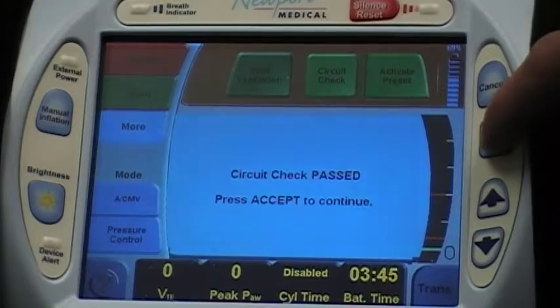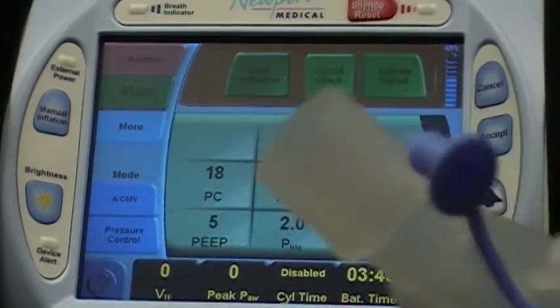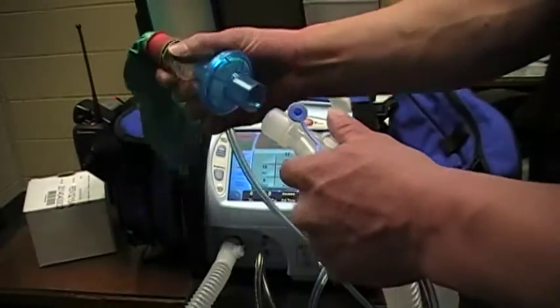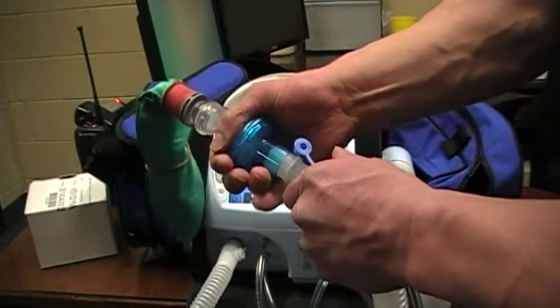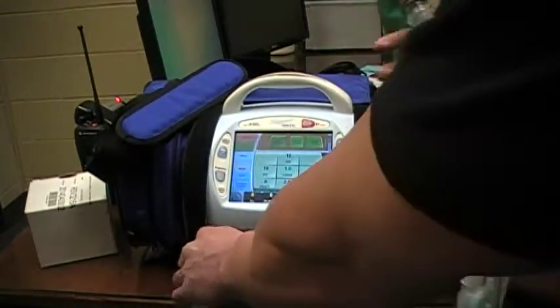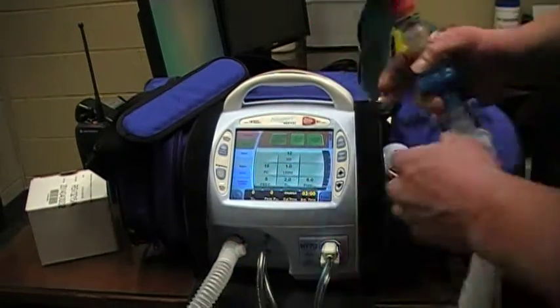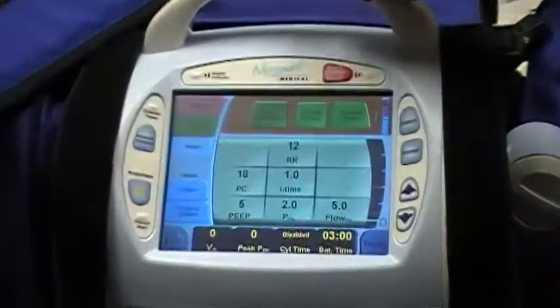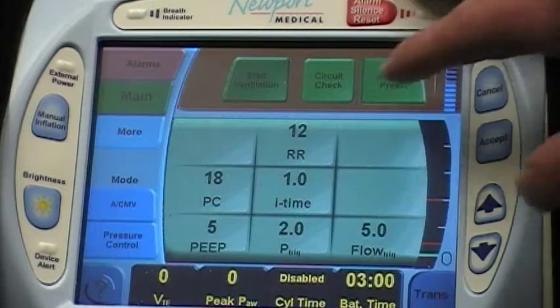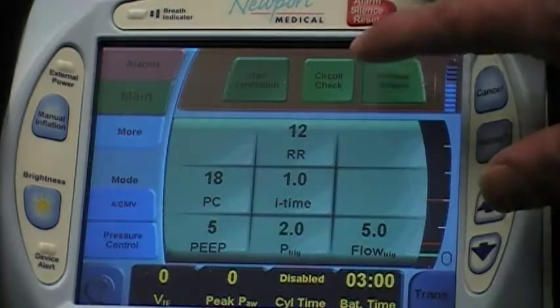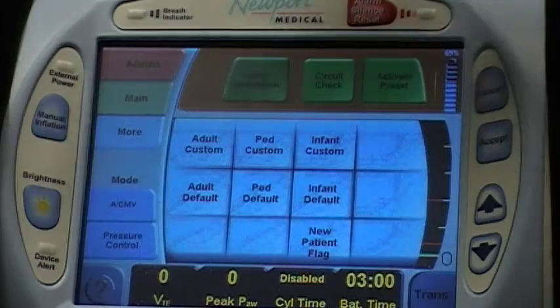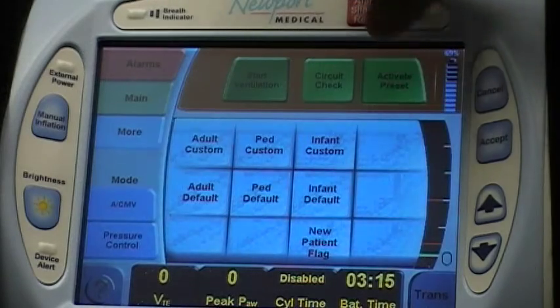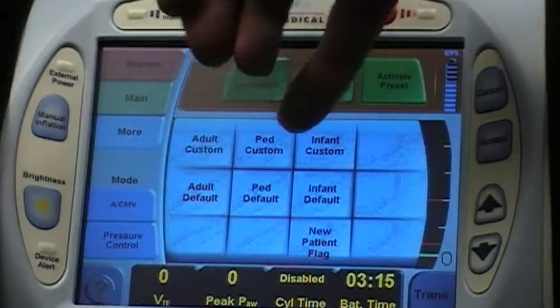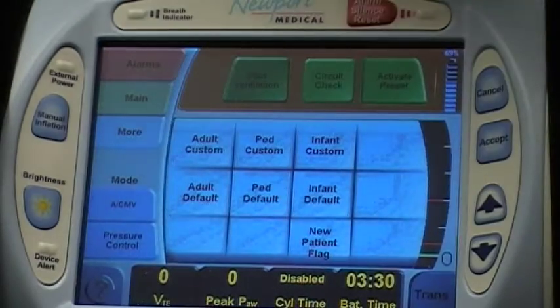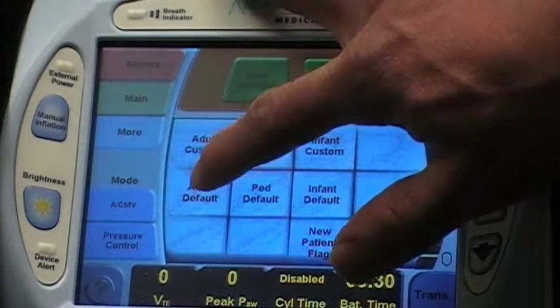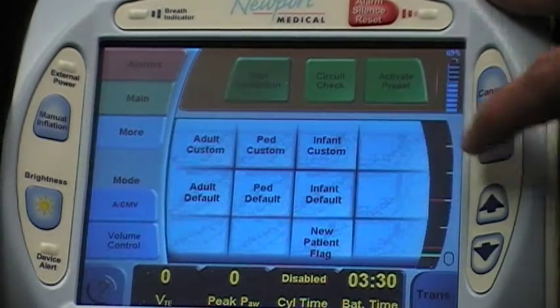Press accept to continue. I'm going to go ahead and put my lung back on here with my filter, with my flow sensor. Everything's tight. Alright, so we've checked our circuit, we've got our start ventilation here, and then we have an activate preset. We can hit that and go in, you can customize presets, and you can also go to the defaults that the vent has. So we have our adult default, so I'm just going to hit that and push accept.